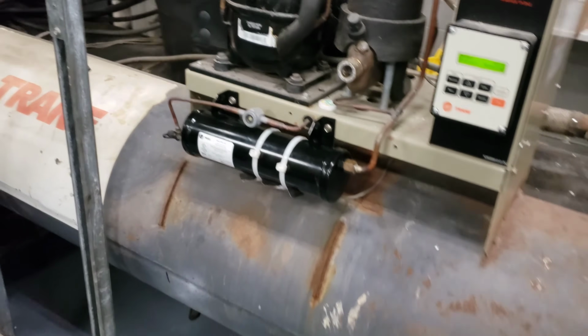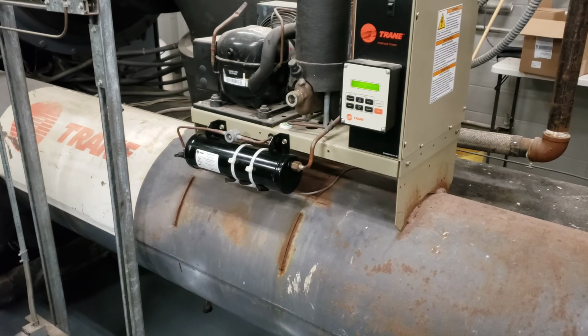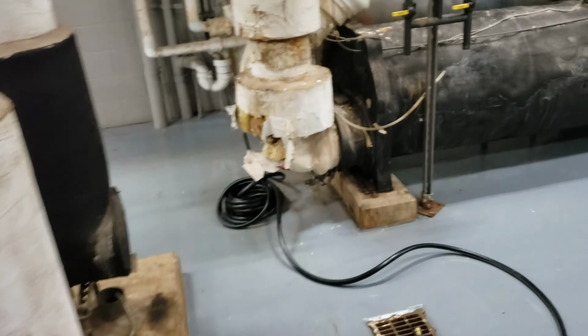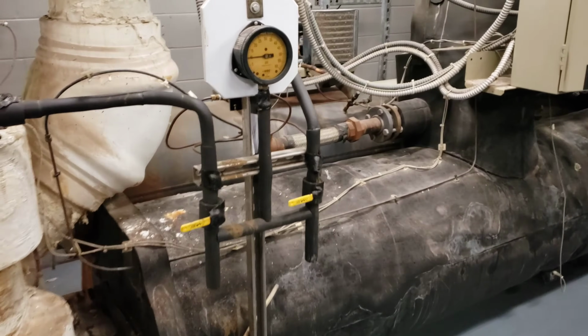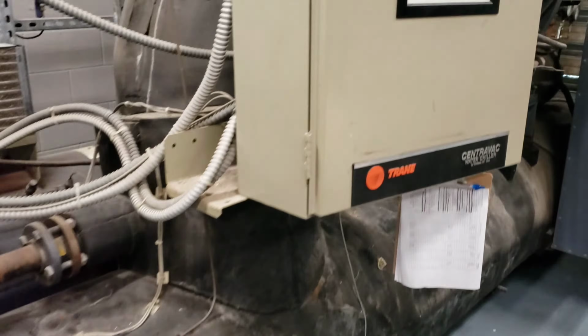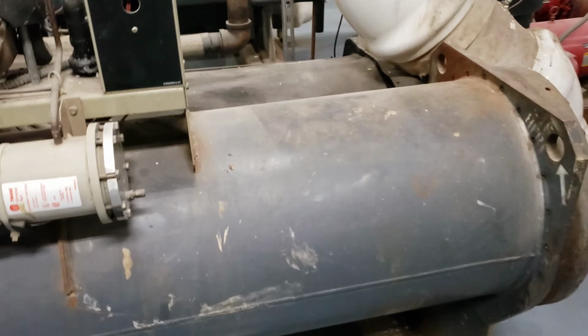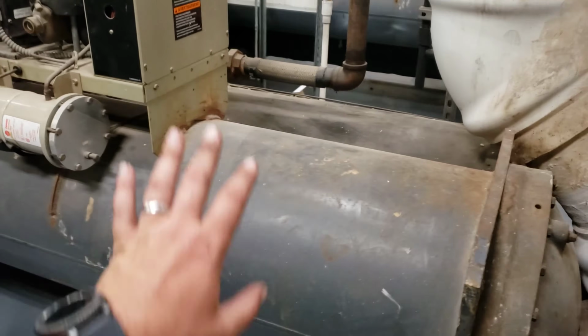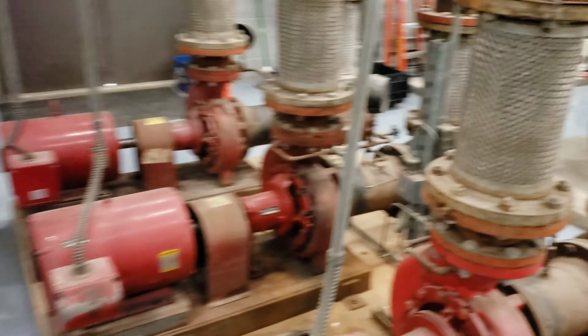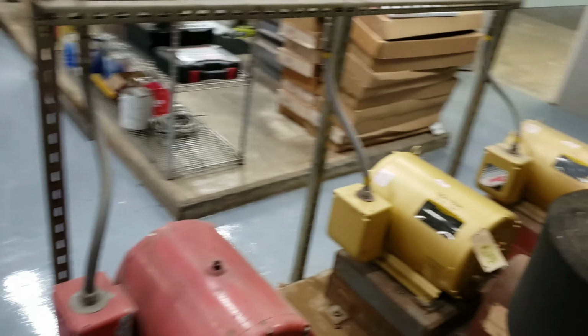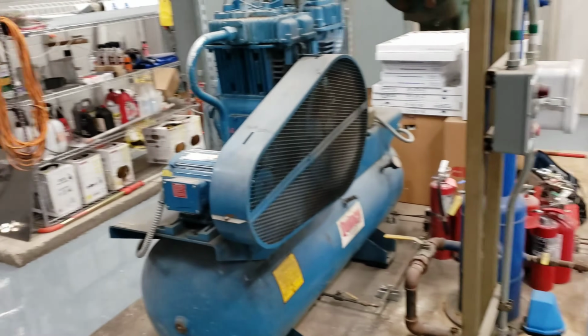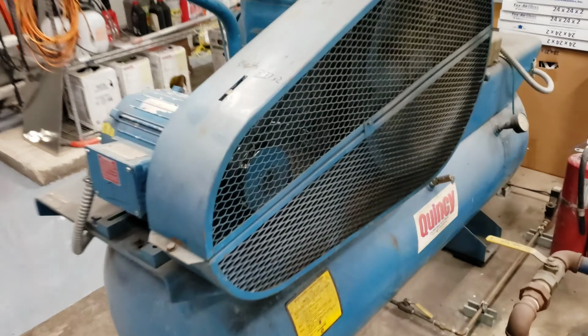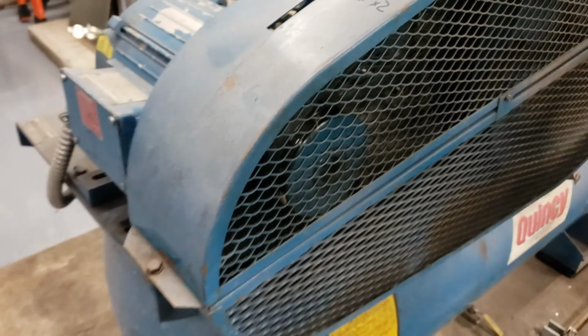Here's some old chillers. So I got 2 plants here. This is the one plant. We're going to be doing some eddy current testing tomorrow. So I got this chiller here draining down, getting ready for eddy current. This has been the primary chiller that's kept up with the building. So this chiller here in the middle has been having a lot of issues, so it's on the projects list to get taken care of. We got 3 condenser water pumps, 3 chill water pumps. There's a lot of pneumatics. You can see that air compressor has got a thrown belt.